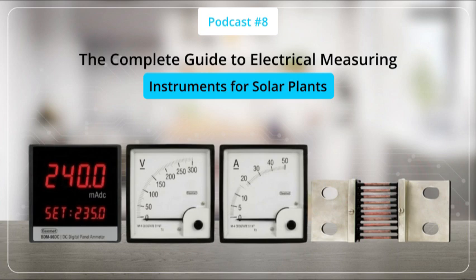Energy meters, on the other hand, record how much energy has been produced or consumed over time, which is essential for net metering and long-term performance tracking. Ground testers verify that the system is properly earthed, which is a fundamental safety requirement. Reference cells measure soiling losses, the power reduction caused by dust and dirt accumulating on panels. And in laboratory settings, solar simulators provide controlled artificial sunlight for testing panels before they go into the field. Finally, data loggers tie everything together by continuously recording multiple system parameters over time. Now, let's understand how these instruments come into play at different stages of a solar project.